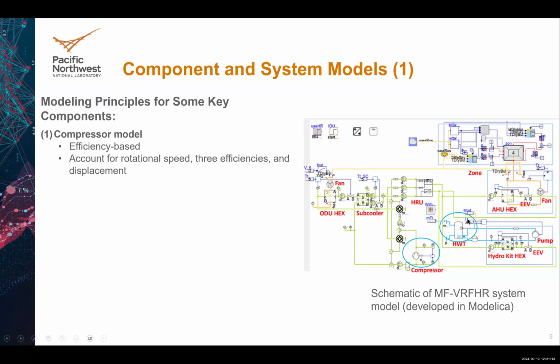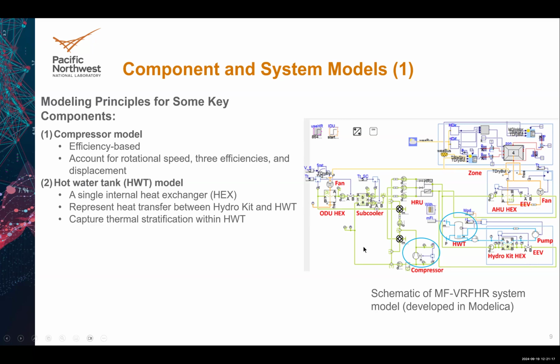Next one, I'll talk about the hot water tank. The hot water tank model has a single internal heat exchanger representing the heat transfer between this tank and the hydro kit. We said this hydro kit is a water to refrigerant heat exchanger. So the water can be circulated between the hydro kit and the tank to heat up the tank when you have domestic hot water requirement. Meanwhile, the model is able to capture the thermal stratification within the tank. That's a very important feature, because usually you will withdraw water at the upper layer of the tank, but you have city water coming in at the bottom of the tank. There are also other configurations, but this is usually the typical configuration for the residential hot water tank.